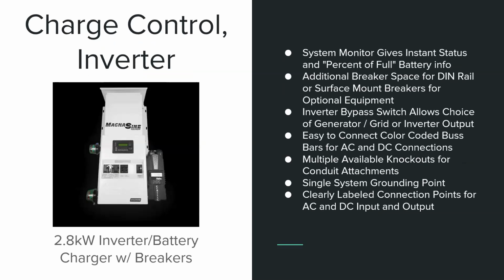Now we have a charge control and inverter system here. This one's designed for 2.8 kilowatts, and it comes with breakers on the front, so you can breaker your inputs and your outputs, which is awesome for isolation purposes. Also, this has a breaker for your line input to charge your batteries remotely or from the grid. There's a system monitor on it that gives instant status and percent full battery info.